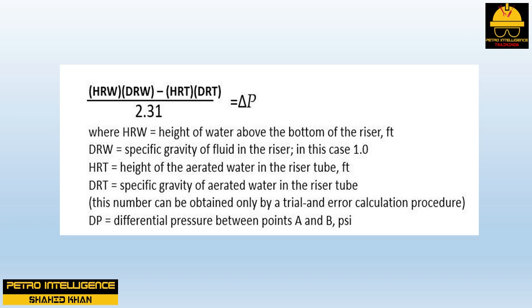We can calculate the pressure difference between points A and B as follows: (H_rw × D_rw − H_rt × D_rt) / 2.31 = ΔP, where H_rw equals height of water above the bottom of the riser in feet, D_rw equals specific gravity of fluid in the riser (in this case 1.0), H_rt equals height of the aerated water in the riser tube in feet, D_rt equals specific gravity of aerated water in the riser tube. This number can be obtained only by a trial-and-error calculation. ΔP equals differential pressure between points A and B in psi.